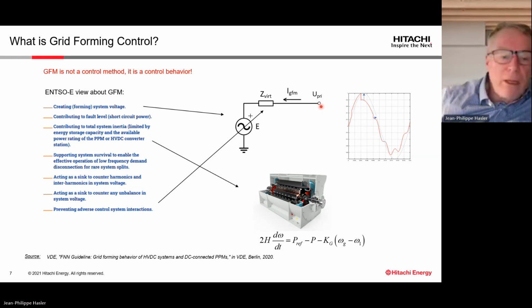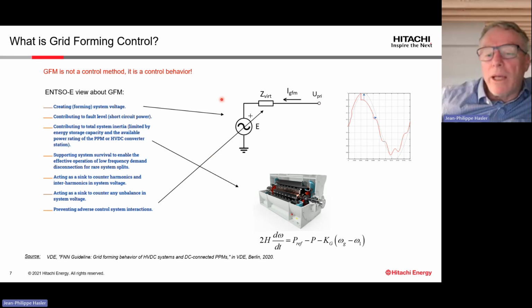high phase jump. But basically, our control will behave exactly as a generator, which also means that when we have resonance in the grid, you provide a parallel impedance to your grid, defined by this virtual impedance, to damp the resonance. That is what I'm showing here. If you have distortion in your voltage, through this impedance you define, you will automatically maintain the voltage at an ideal sine wave.